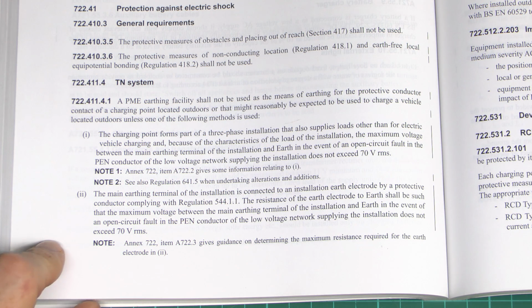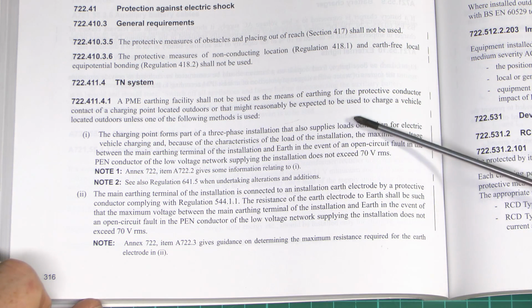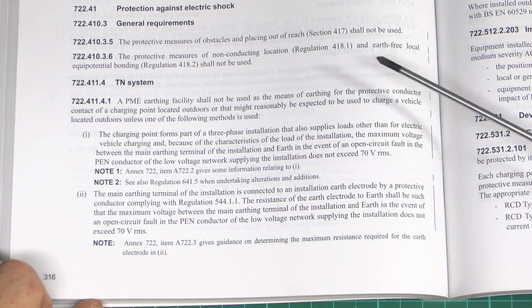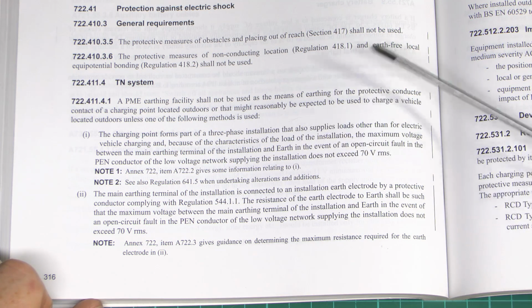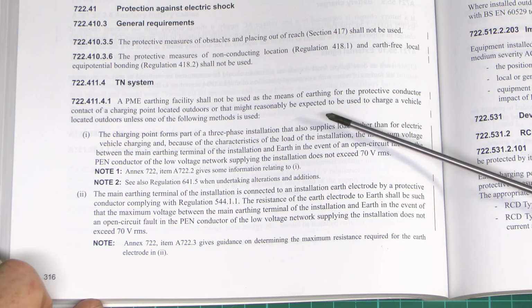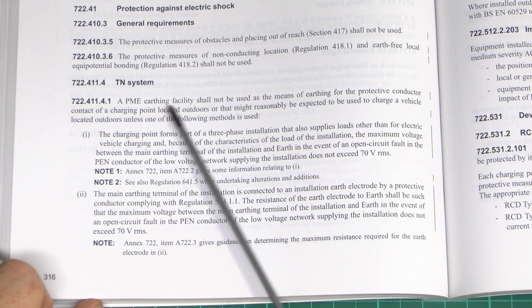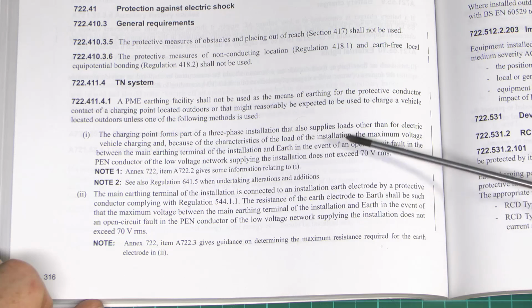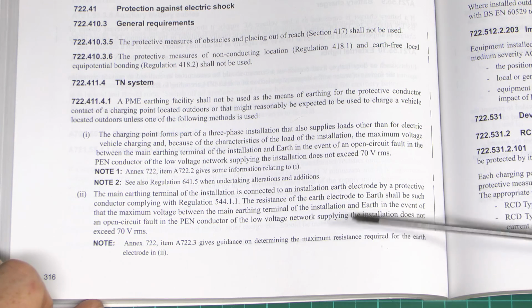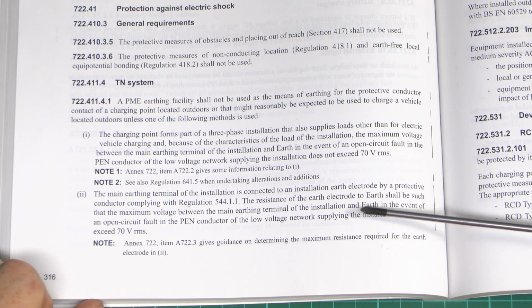And bearing in mind, even if you stick the thing in somebody's garage, it's fairly likely they're going to just park the car on the drive and plug it in there. So even if there is the presence of, say, a garage or whatever, in reality it's going to be equivalent to considering it to be done outside. Now, for practical installations, the earthing facility for PME will not be used because, as we'll see in a moment, these three things here, this one, and the one on the next page, are so desperate and unlikely and impossible to comply with that you're not actually going to be using these things.